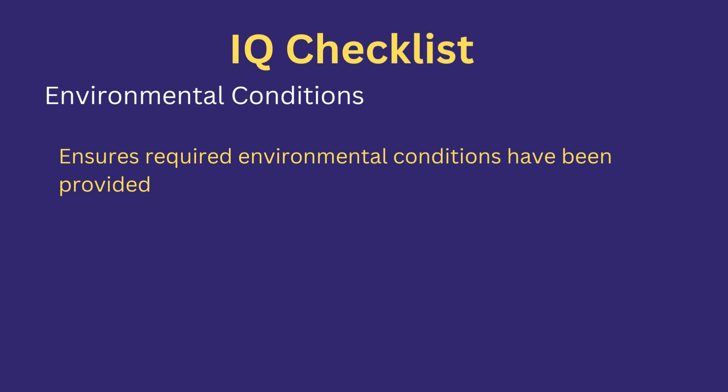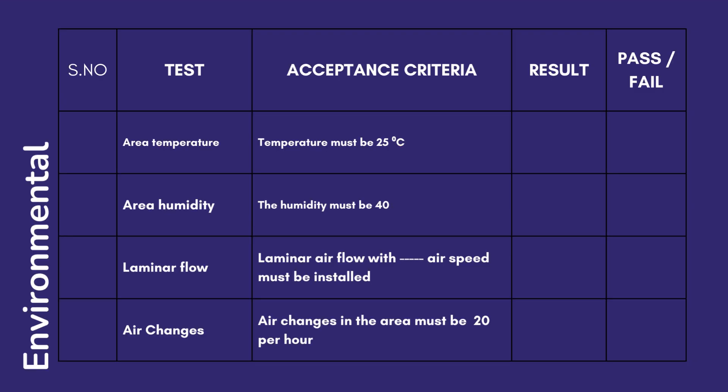Environmental conditions: in this test, different environmental conditions are verified which are vital for satisfactory equipment operation. The possible checklist could include: Area temperature — must be 25 degrees centigrade. Air humidity — humidity should be 40%. Laminar flow — laminar airflow with desired airspeed must be installed. Air changes — air changes in the area must be 20 per hour. Differential pressure — must be 30 Pascals. Area classification — the area for production must be Class A, B, C, or D.